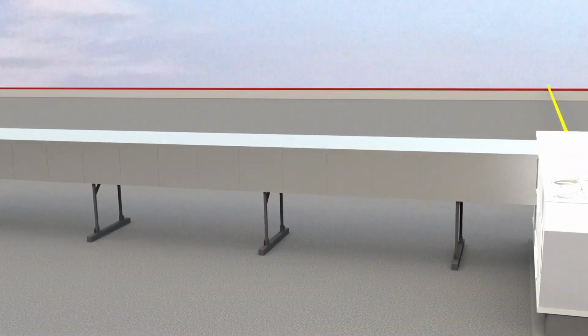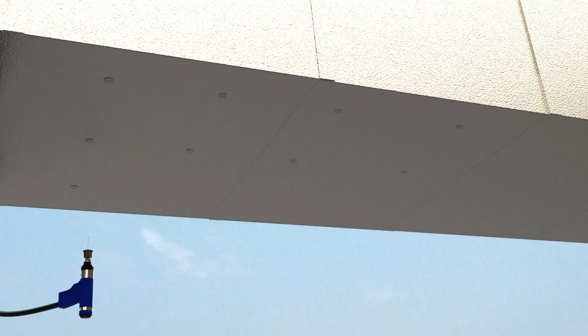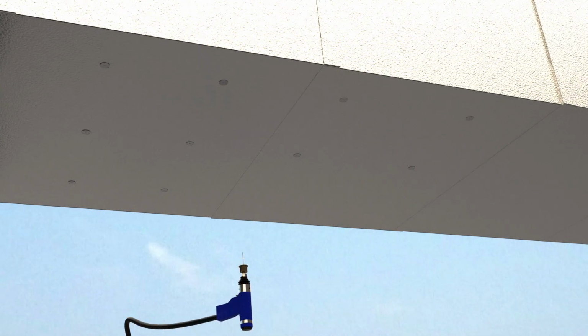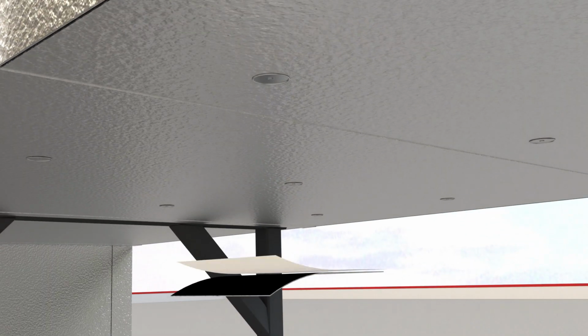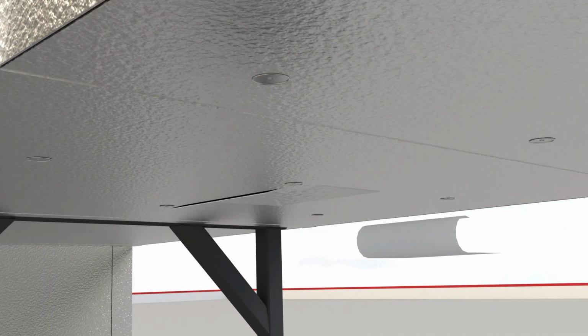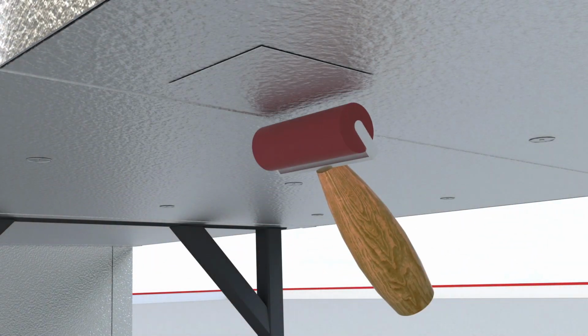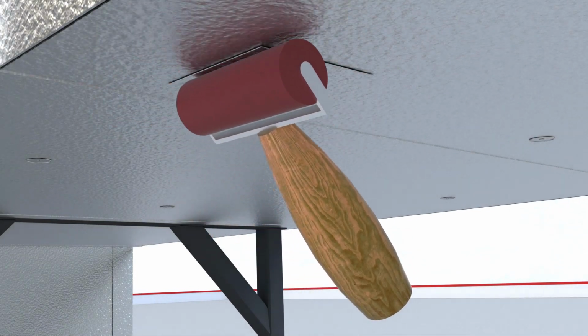Several installation items need addressed when considering the underside of the ductwork. Due to the weight of the material, MFM recommends the use of stick or weld pins on ductwork over 24 inches. These should be placed every 12 inches on center. Cut 3-inch squares of FlexClad to cover the heads of each pin to avoid water penetration. Be sure to hand roll each square into place.